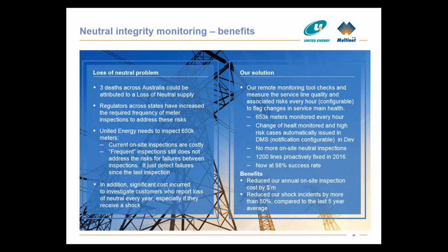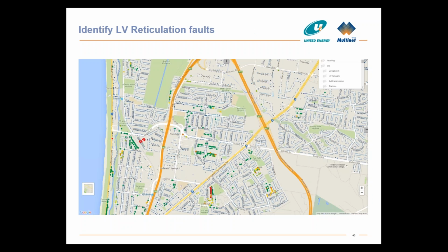Our algorithms are currently running at a 98% success rate, so very few cases can't be found. If they can't, it's usually a case where we send the crew back a second time and they find it then. So instead of doing inspections at a high frequency—sometimes 5 year, sometimes 10 year cycles—we can do this remotely. We run the analytics every hour, and typical detection time to confirm an issue is about 4 hours. So instead of waiting 10 years, we can now get the fault truck out there within 4 hours and fix it.